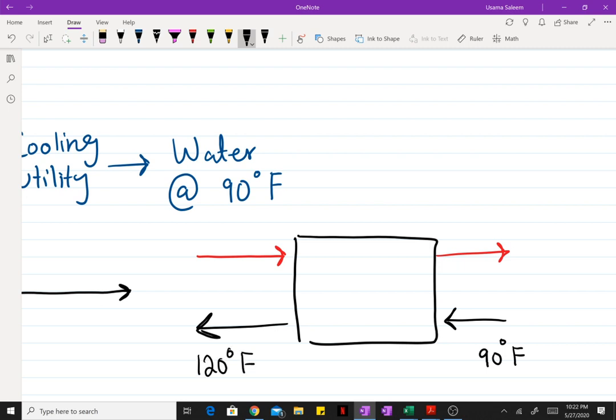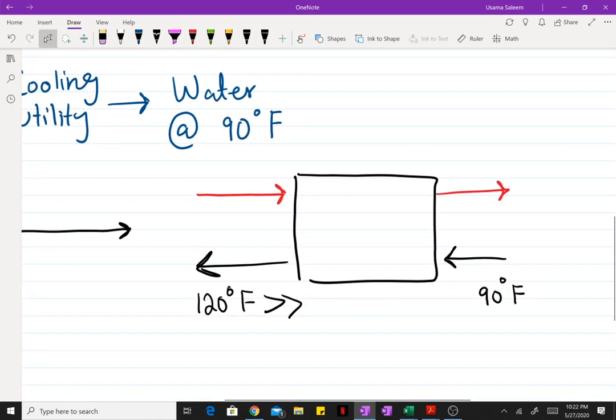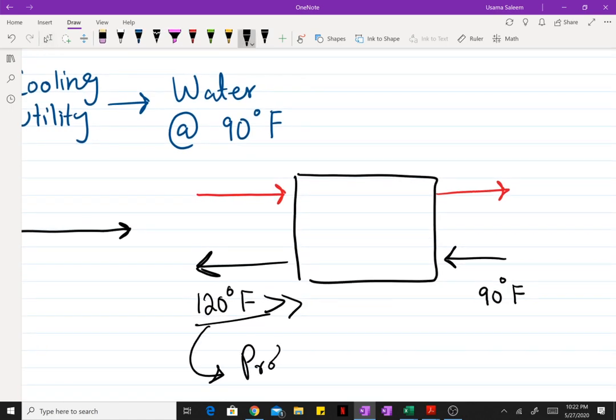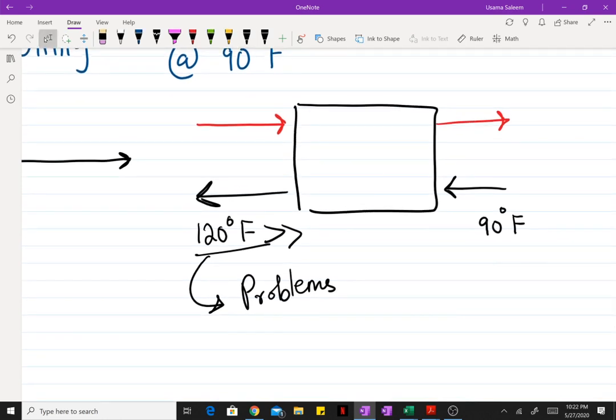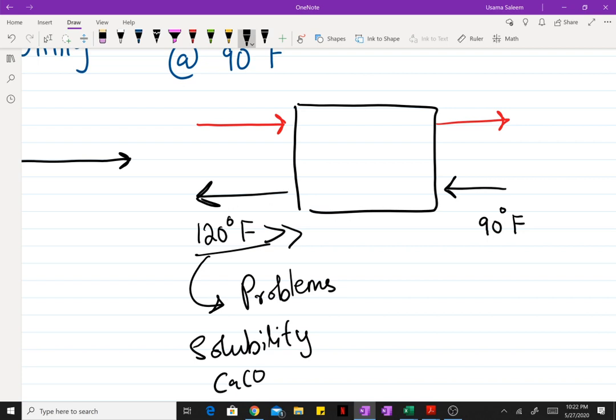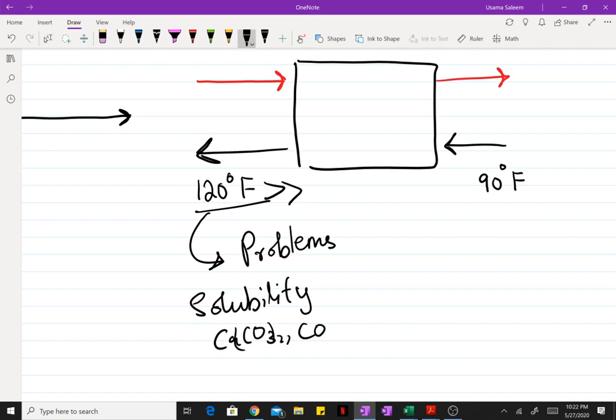If the temperature of cooling water exceeds 120°F, this leads to problems. At temperatures above 120°F, the solubility of various salts like calcium carbonate and calcium oxide increases, meaning minerals and salts become highly soluble in water, and this can lead to fouling in the condenser.